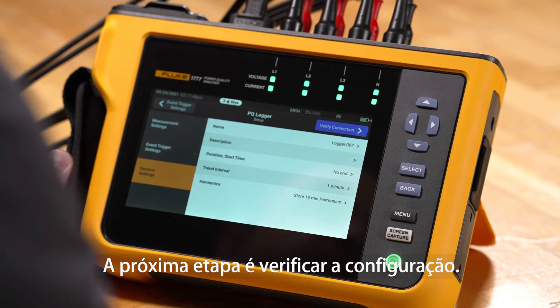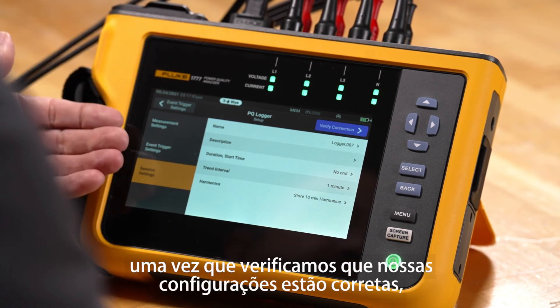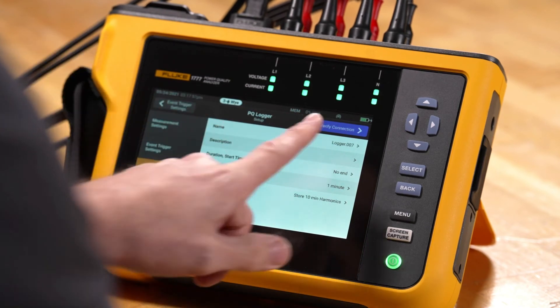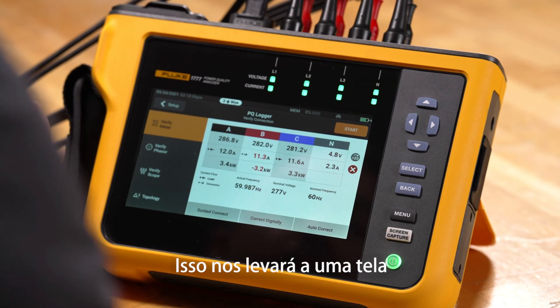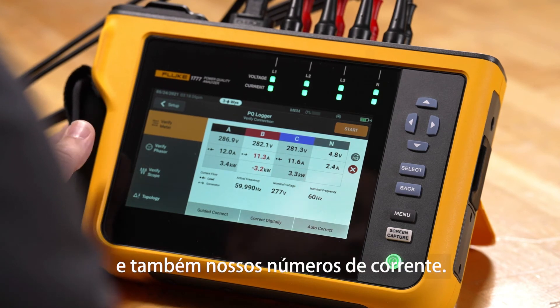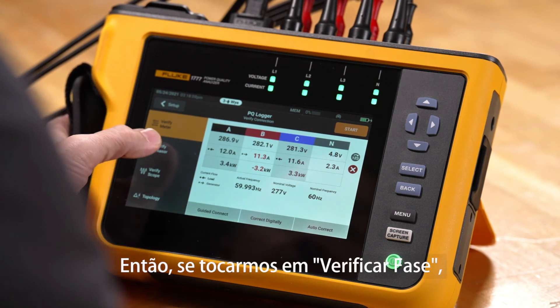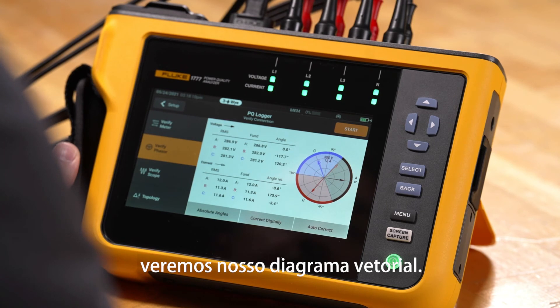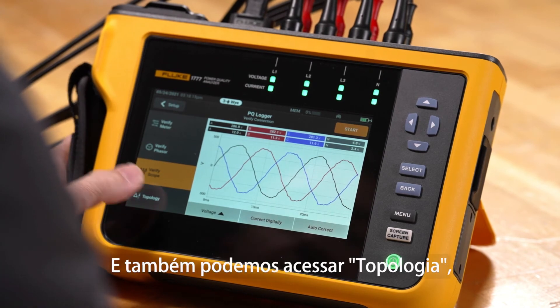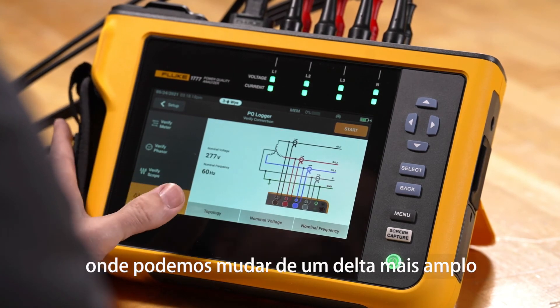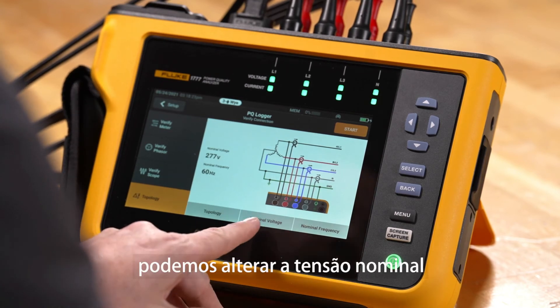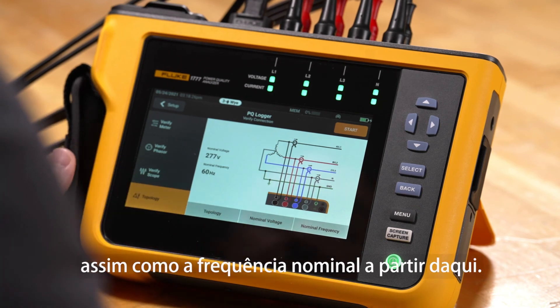The next step is to verify configuration. Once we've verified our settings are correct, we go to verify connection on the screen and tap verify connection. That puts us into a screen which shows our live active voltages, our power, and our current numbers. If we click verify phasor, we get our vector diagram, and we can also go to verify scope and look at waveform data. We can also go to the topology where we can change from a Y to delta configuration if needed, and we can change the nominal voltage as well as the nominal frequency from here.